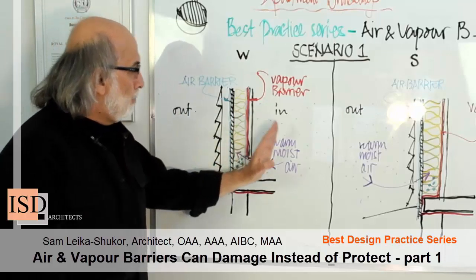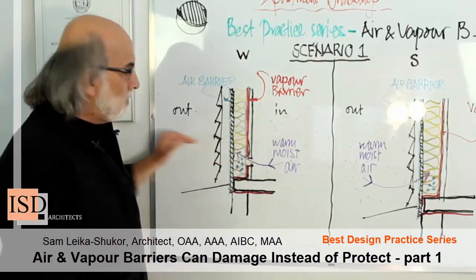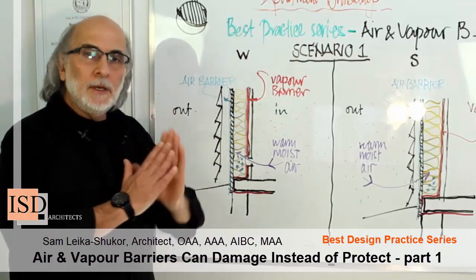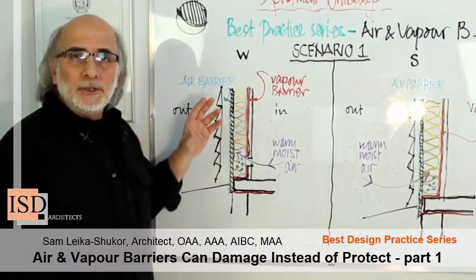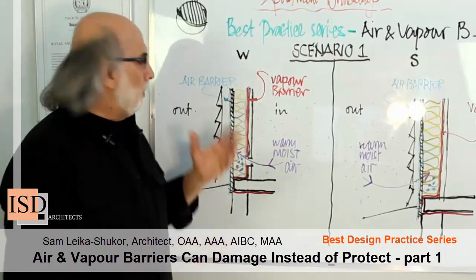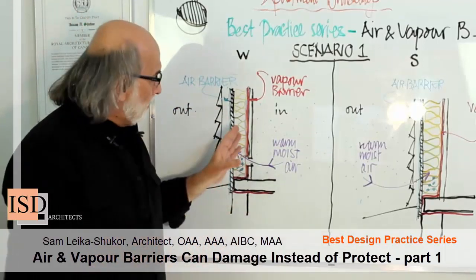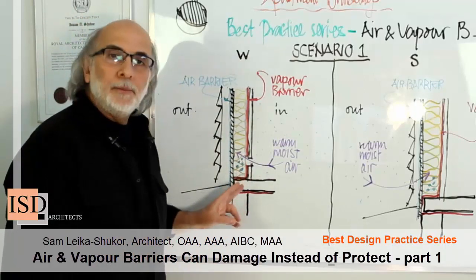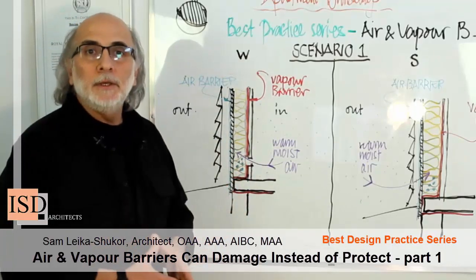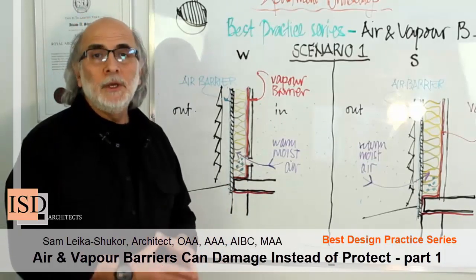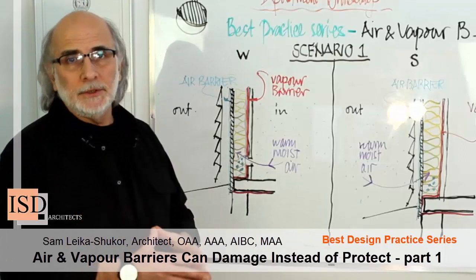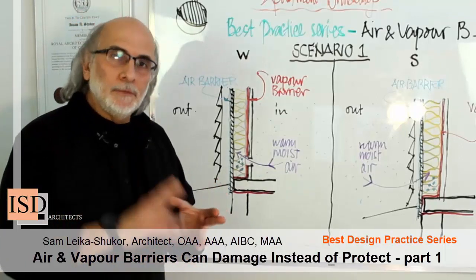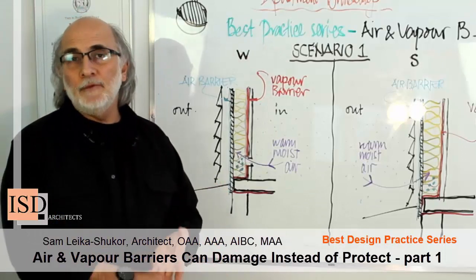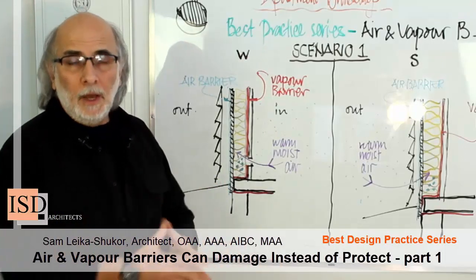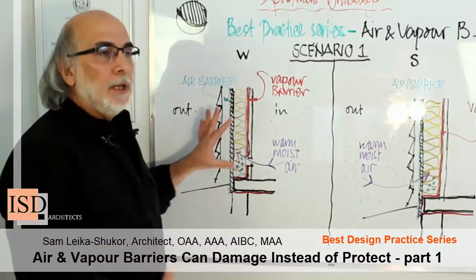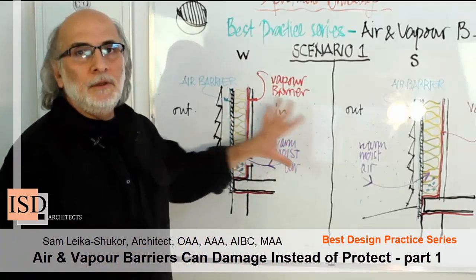So the more the air penetrates from inside towards the outside, it will face cold surfaces. This condensation would turn the gas state of the vapor into liquid state, which is water. And then the water would drop at the bottom of the wall, causing serious issues with mold. And mold is highly hazardous, especially for children and for the elderly and for people who have asthma or any other illnesses that could impact negatively the environment.